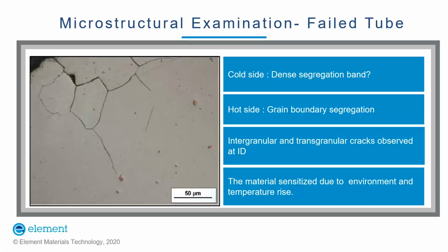Additionally, the microstructure at the crack location showed that the crack appeared to originate at the ID, the internal surface at the hot side of the tube. The crack morphology appeared to be both transgranular and intergranular, which is a very typical feature of a stress corrosion crack. It can be established from the above study that grain boundary segregation resulted in sensitization of the tube at the hot side due to high temperature and environmental conditions. This sensitization led to stress corrosion cracking (SCC) in the tube under adverse operating conditions. This finding also implies that the operating condition of the heat exchanger was not properly monitored, and the temperature might have risen beyond 500 degrees, which is the specified operating condition of the heat exchanger.